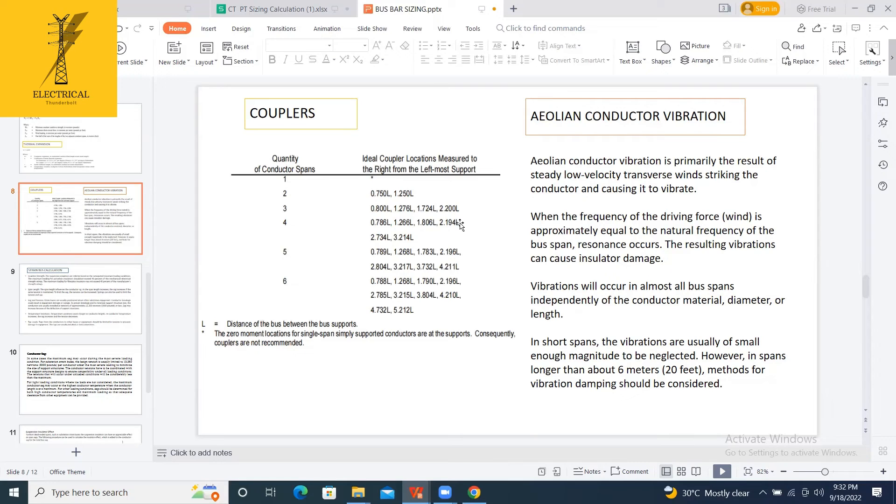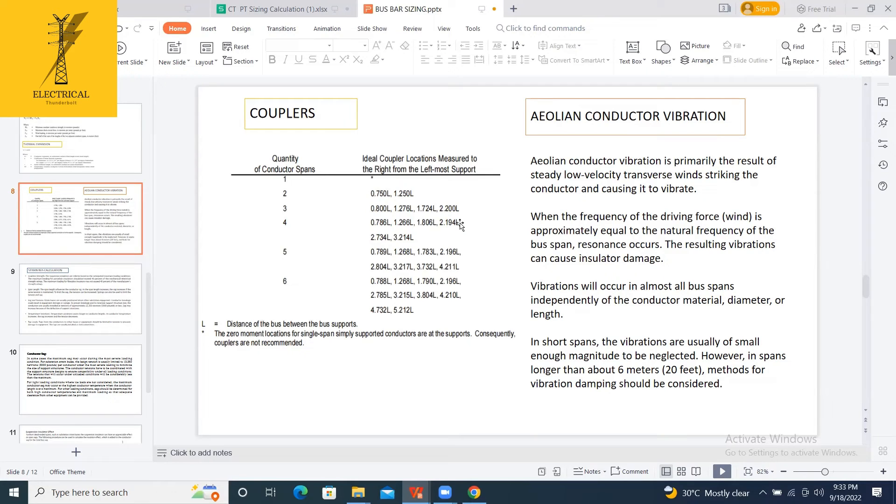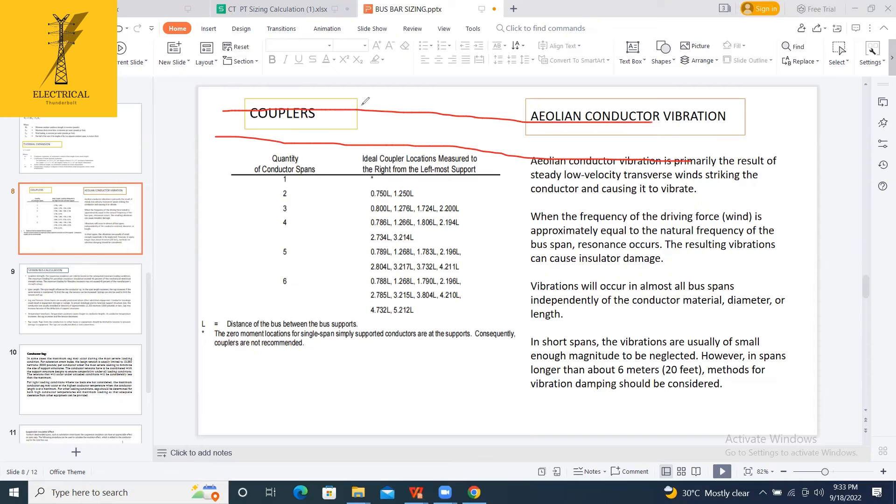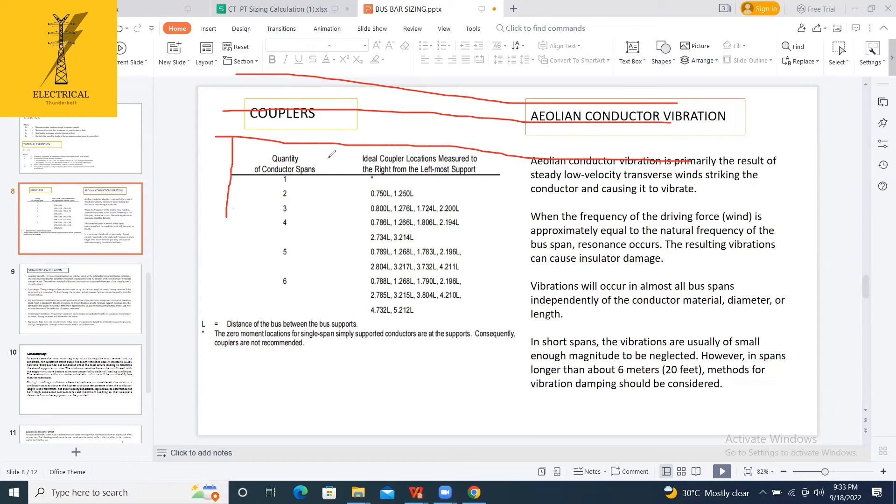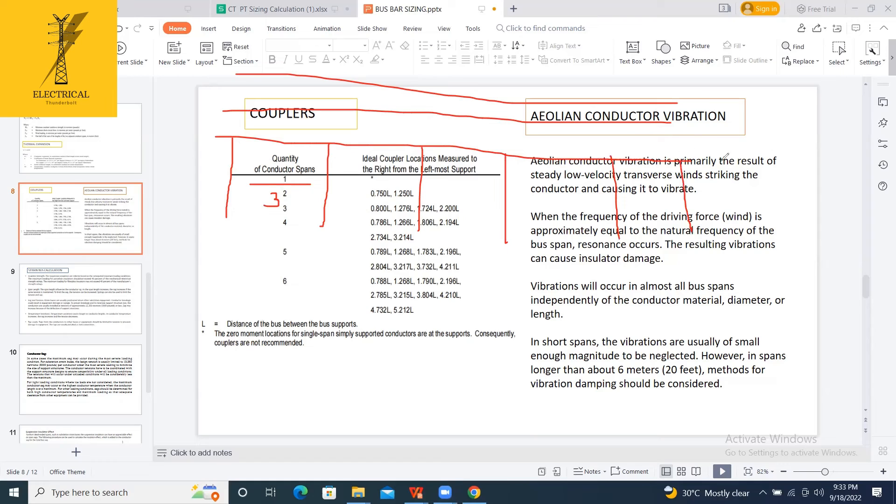Now, I have to erect that 4-inch aluminum pipe on the site, which is for, suppose, a 20-meter length of the pipe I have to install. For this 20 meters of the pipe, for R phase, Y phase, and B phase, at present I am assuming that the spacing between the supports, at present I am assuming as 3 meters. With 3 meters apart, I am calculating.